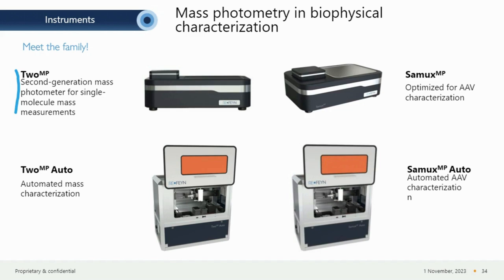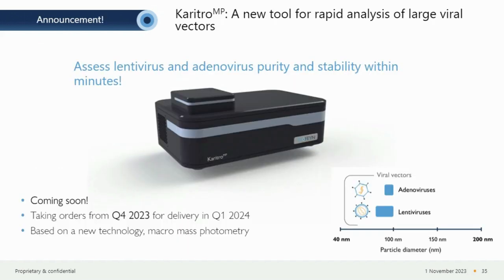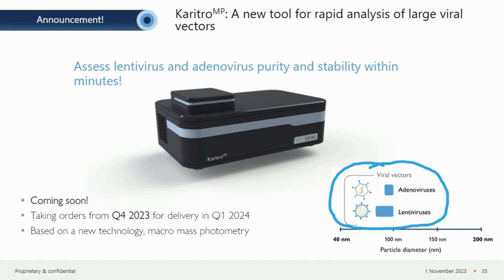I'm excited to announce that Refeyn is extending our family of mass photometers with a new tool for rapid analysis of large viral vectors: the Karitro MP. This benchtop instrument allows assessment of lentivirus and adenovirus purity and stability within minutes. It will be coming to market soon — orders are being taken now for delivery in the first quarter of next year. The Karitro MP is based on a new technology called macromass photometry, required because these viral vectors have much larger particle diameters of up to about 100 nanometers, which cannot be measured by standard mass photometry alone.